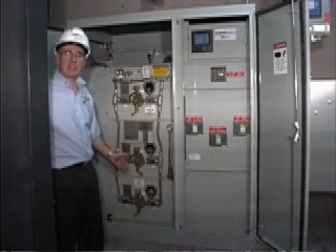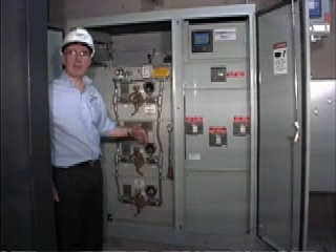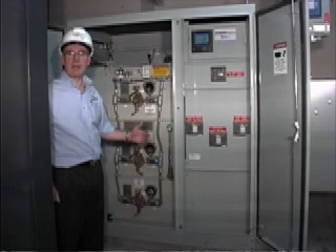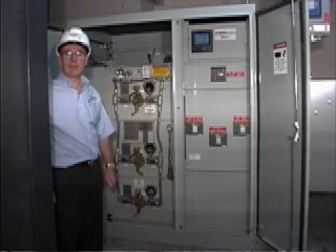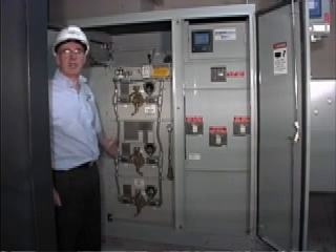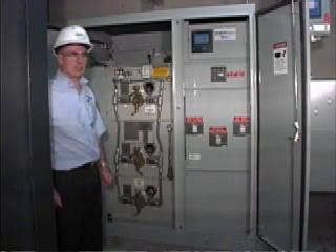Depending on the size of the transformer, whether it be 500 kVA up to 2500, the depth of the unit will increase some, but the width and the height remain roughly the same. And that will include up to, as in this case, three separate 15 kV load break switches.